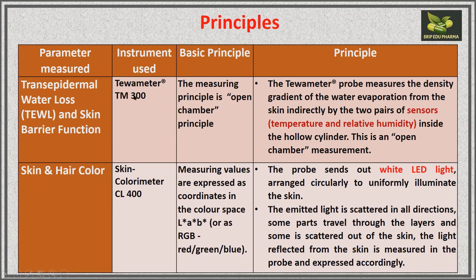For transepidermal water loss (TEWL) and skin barrier function, the instrument used is the tewameter. The measuring principle is the open chamber principle. The probe measures the density gradient of water evaporation from the skin using two pairs of sensors — temperature and relative humidity sensors — present inside a hollow cylinder.